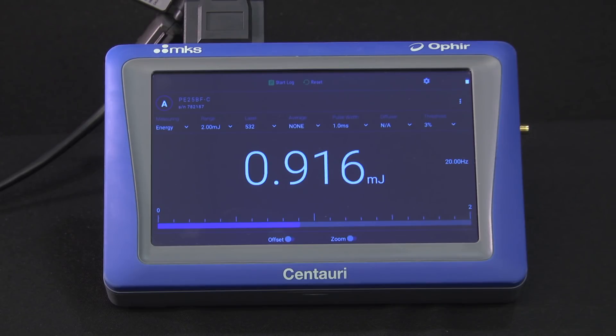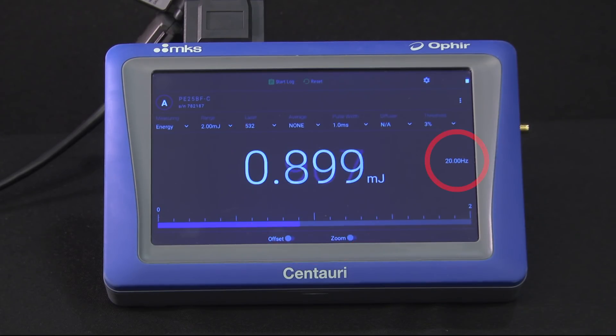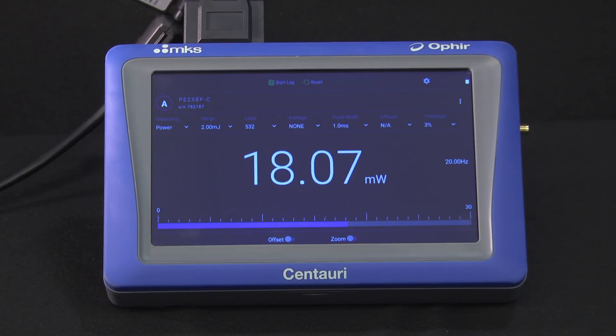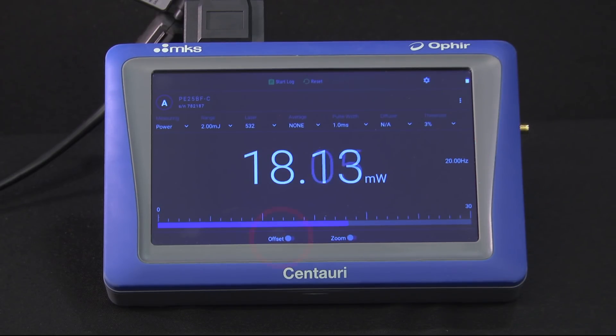When we measure energy, we're shown the pulse energy as well as the repetition rate. In power mode, we're shown the average power of this same beam. Offset, here at the bottom, can be set to subtract a fixed offset from all subsequent measurements, as long as offset is active.